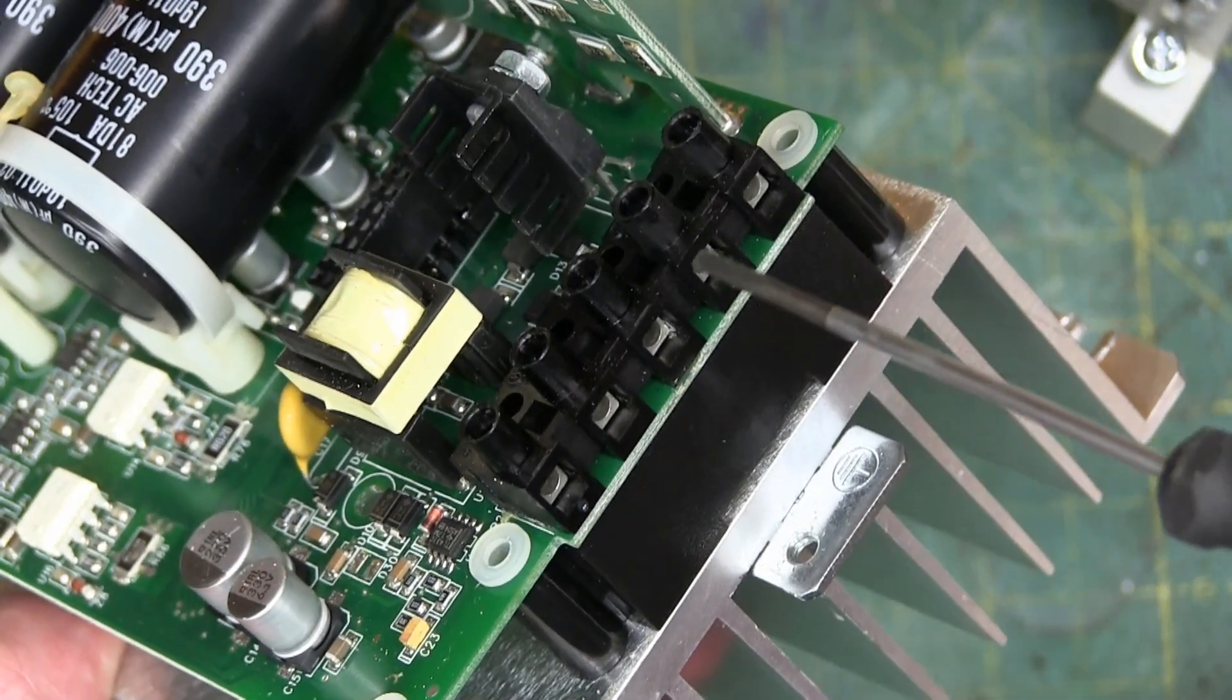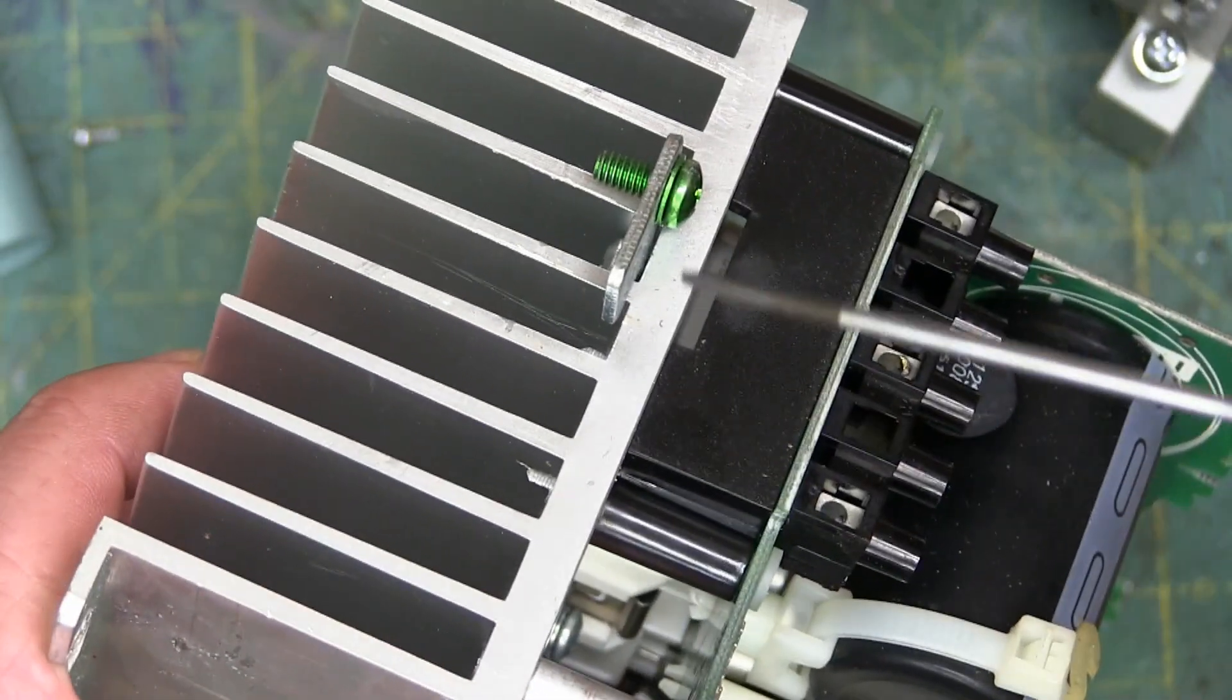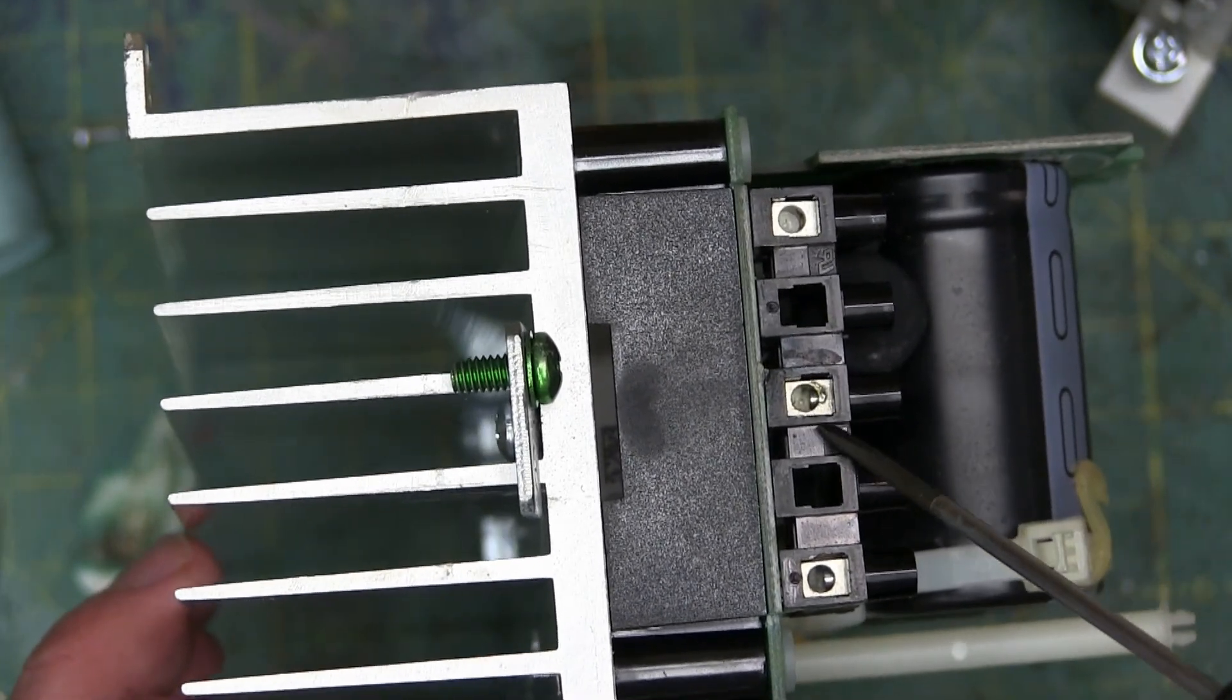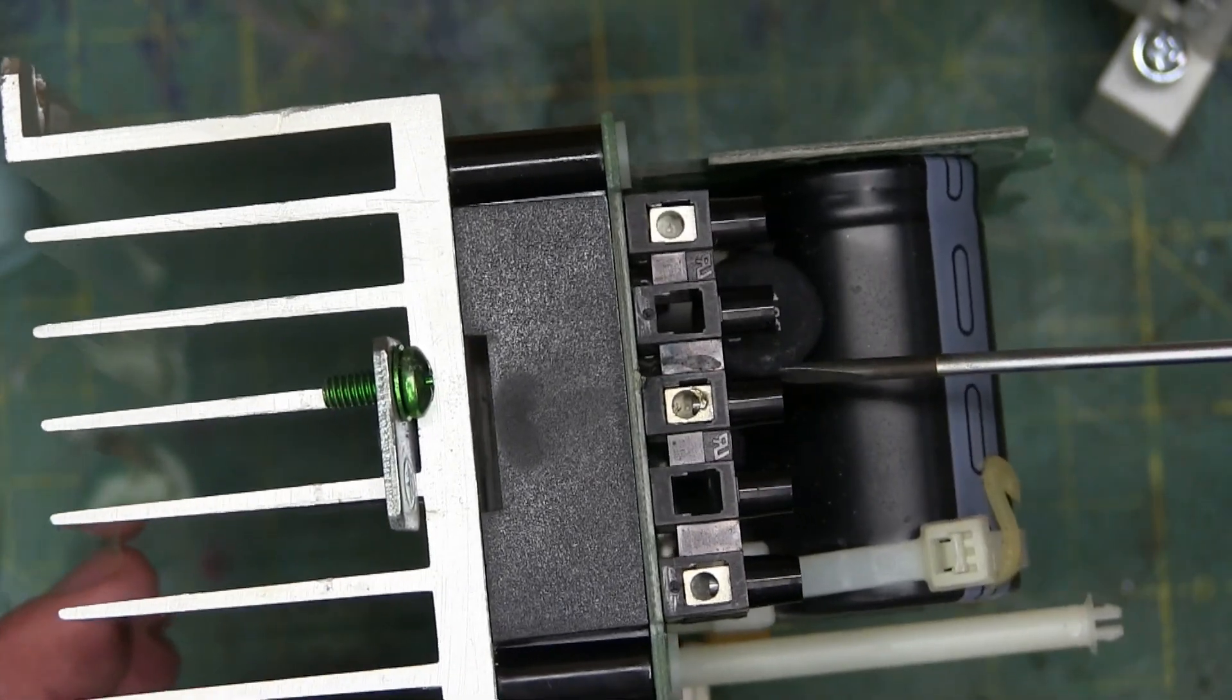So, we have here the first clue as to, well, potential clue, as to what happened to this drive. On the obverse, we got the T1, T2, T3. The T's are designate motor leads. And the L's are the inputs. What do we have here on one of the phases? Big old arcing and a sparking happened in there. So, either they did a hot swap and somebody got a bit of a start, or this thing was loose. And, of course, a loose connection means high resistance. High resistance means heat. Heat means no es bueno for electronicals.